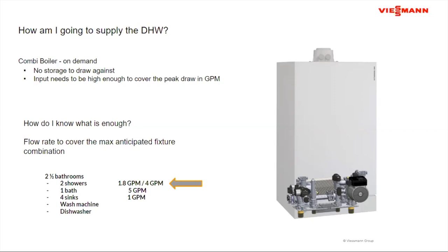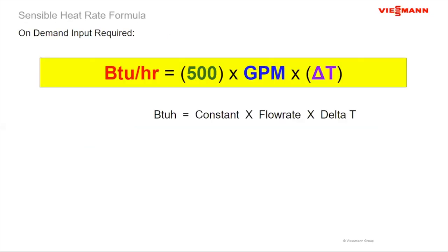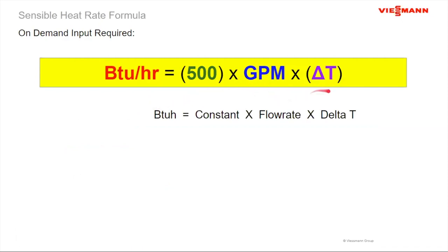With that number, I can then start to calculate what the input and output of the water heating part of the combi boiler has to be. I'm sure this formula is familiar to a lot of people, but it allows me to look at a water requirement in gallons per minute and the delta T, or the differential temperature that I'm trying to raise that water, and I can utilize this to calculate the heat input that's necessary. This formula works in domestic hot water, and is also very familiar to a lot of guys that do calculations for hydronic heating as well.